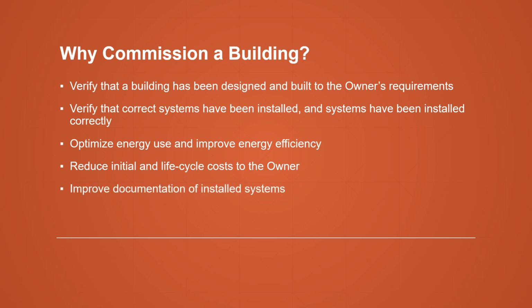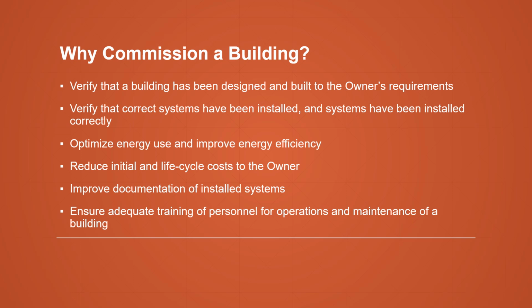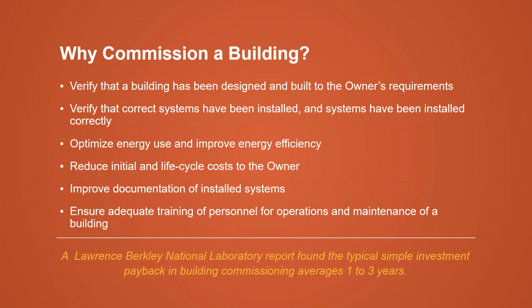It also improves documentation of what systems have been installed, and it ensures the training of personnel to be able to operate and maintain the building once the building has been turned over. Commissioning must not be thought of as an additional cost or unnecessary service. Commissioning is a valuable investment that can lead to long-term financial benefits for the building owners. A report published by Lawrence Berkeley National Laboratory found that the typical return on investment in building commissioning services achieved a payback in an average of 1 to 3 years.